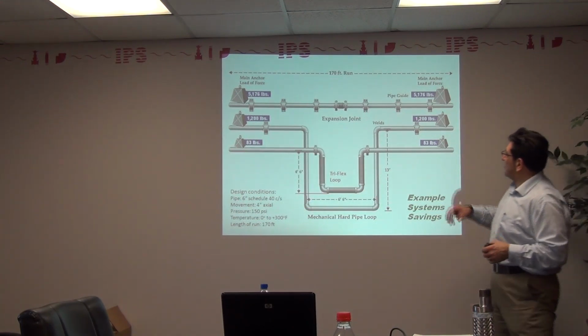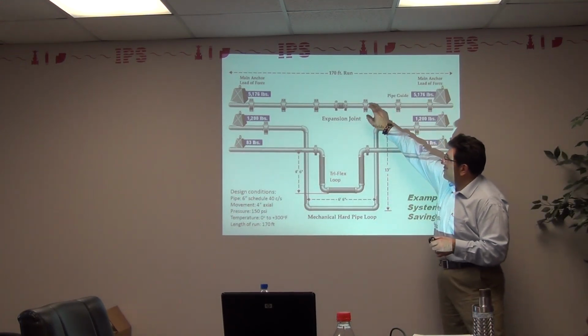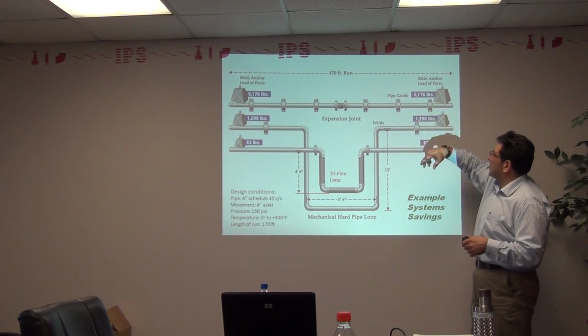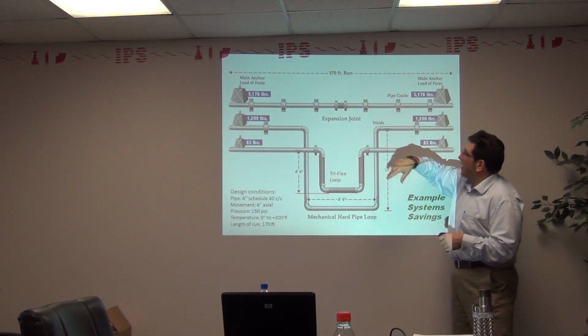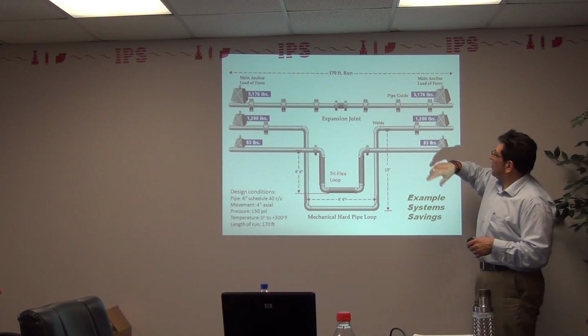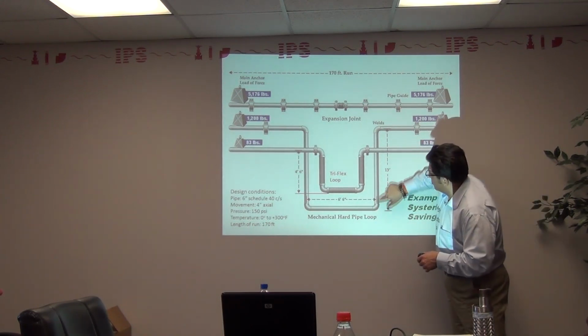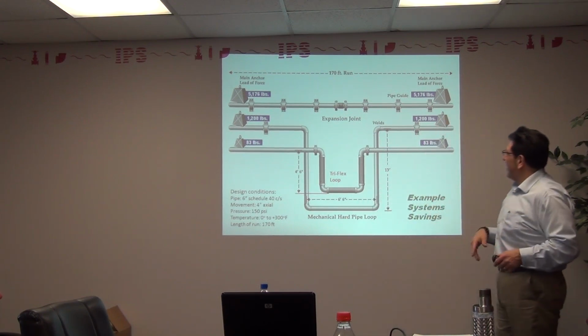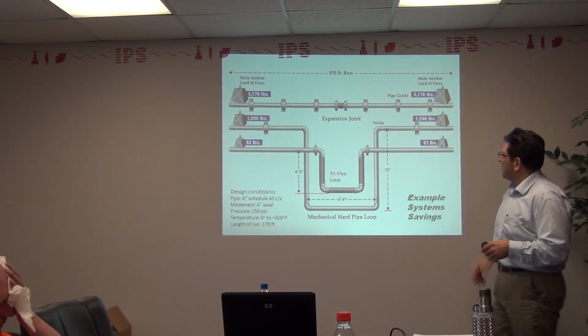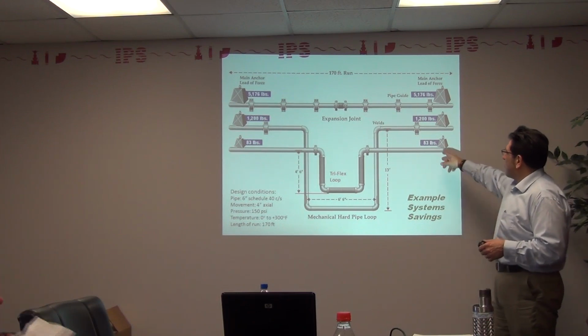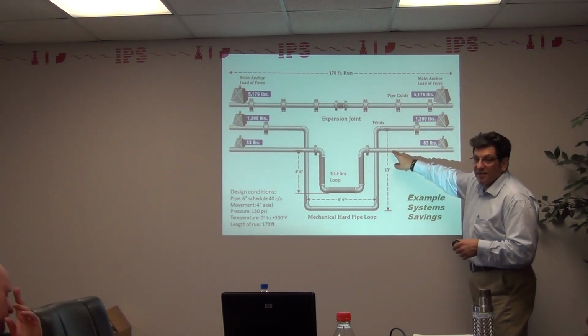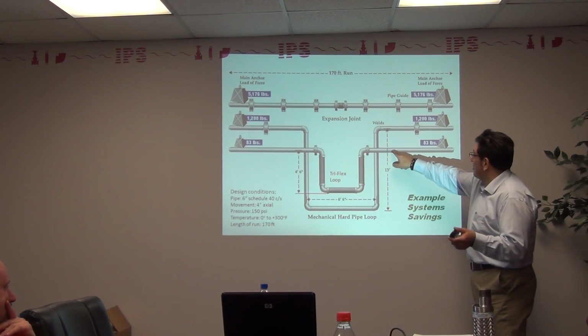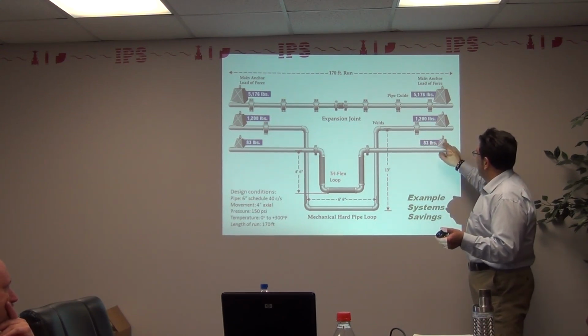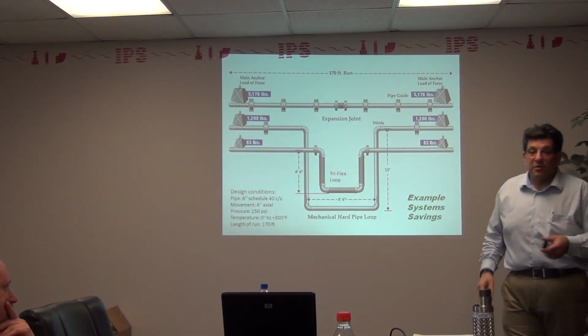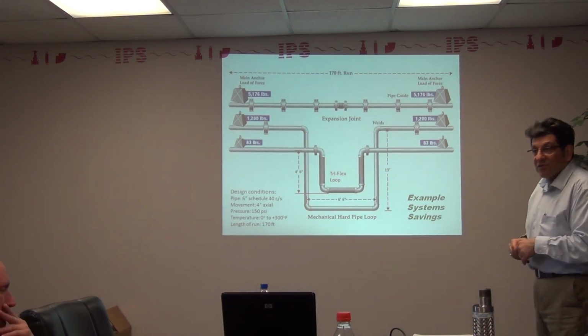Here's the real payoff with this. We talked about previous expansion joints and what their large anchor loads would be, and all the pipe guides someone would have to put in - or if they're going to hard pipe it, you can see all the space and footprint that would take. It's a 2-to-1, and using ASHRAE methodology, their anchor load would be up around 1,200 pounds. With the TriFlex loop, there's no pipe guides necessary because we can take motion in all degrees of freedom, and the anchor load is only 83 pounds - all it is the spring rate of the hose.